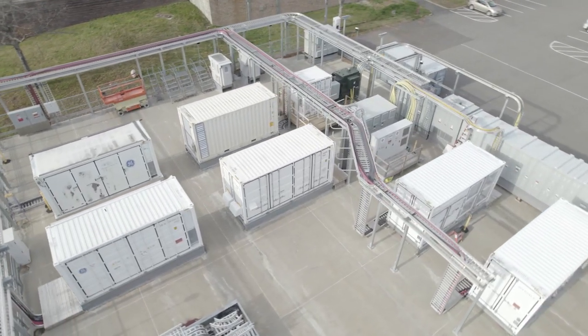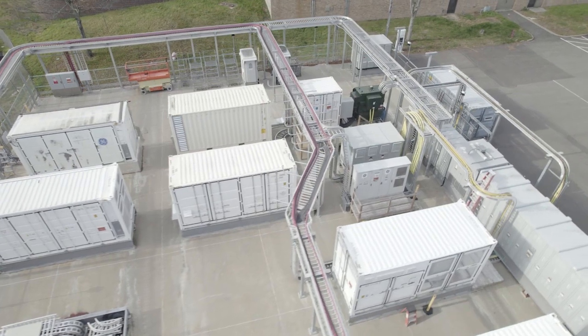Transformers are specified with three main parameters: power, voltage, and impedance. Today's transformers have fixed power, voltage, and impedance. The flexible transformer we have offers three voltage ratings and a variable impedance value. So technically, one flexible transformer can replace any other transformer in the grid or fleet it is designed for. The flexibility is really about having multiple voltage ratings and multiple impedances so they can accommodate grid variation and evolve with the grid.